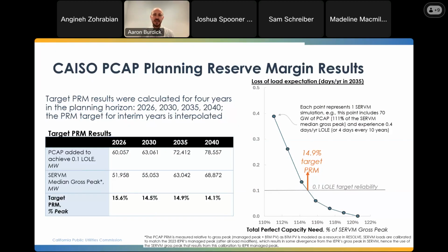On the graph on the right, we have a sample set of analysis from the 2035 PRM study. The way you do a target planning reserve margin study is you take your system, look at different levels of installed capacity, and simulate that system using your loss of load probability Monte Carlo simulations. You can map out the points shown here to draw out this curve.